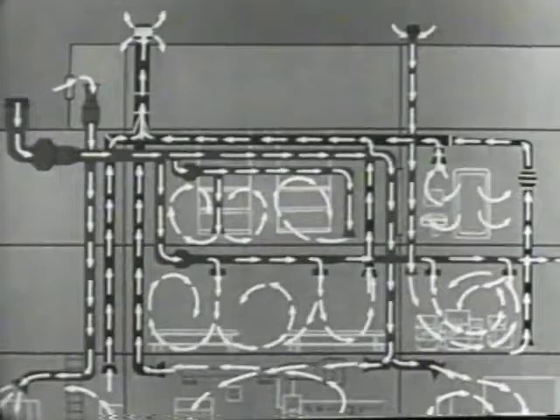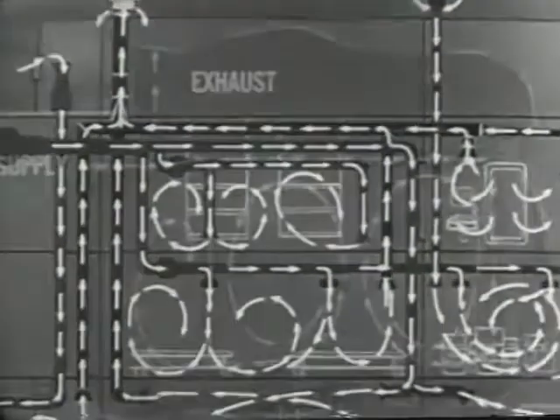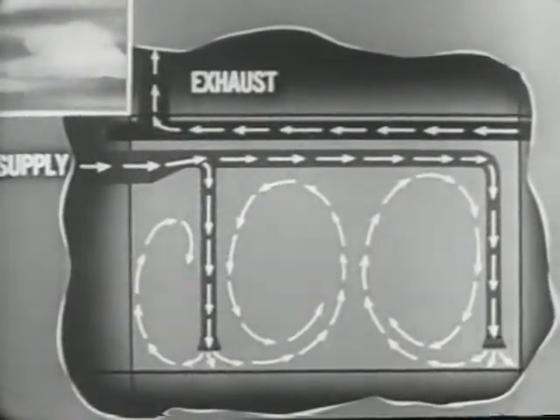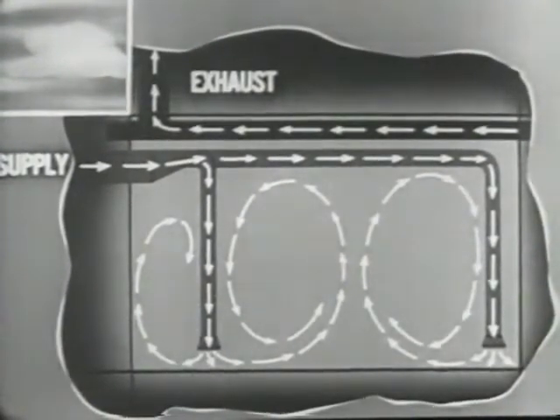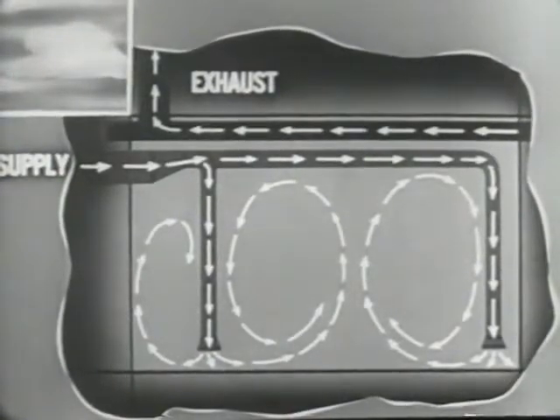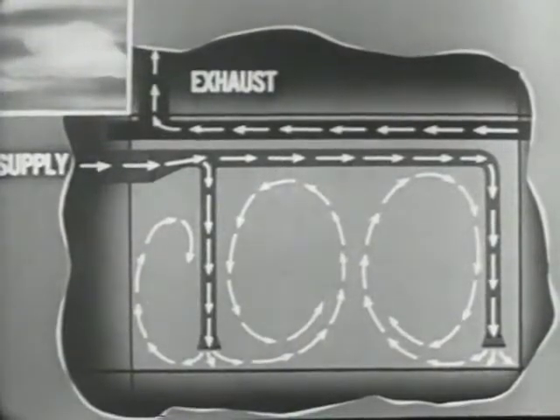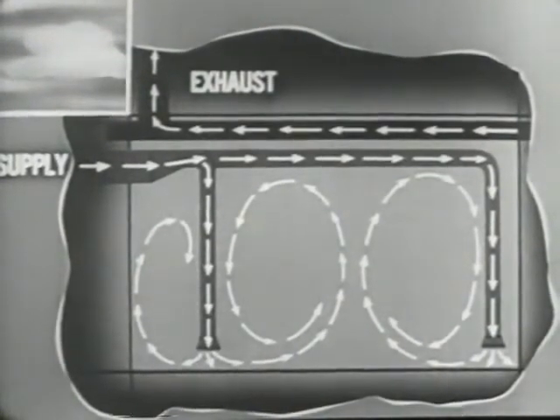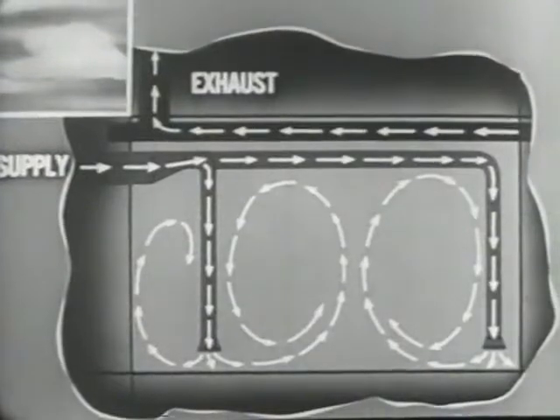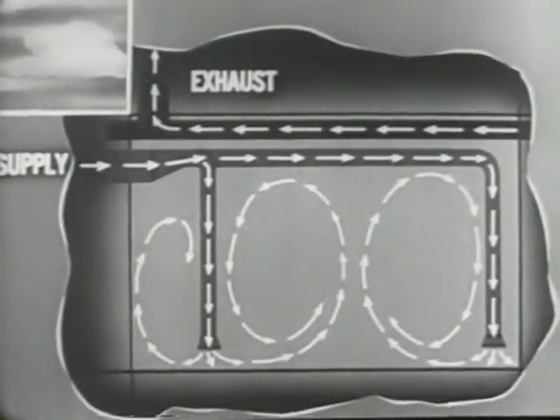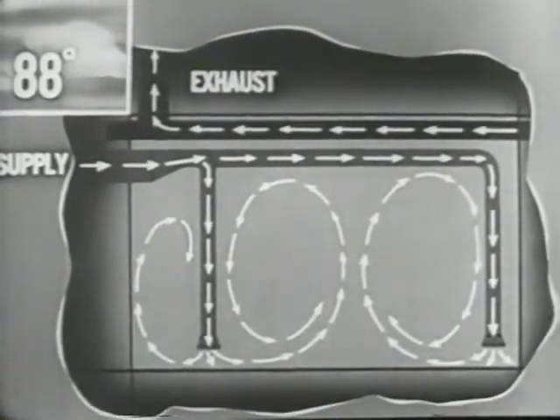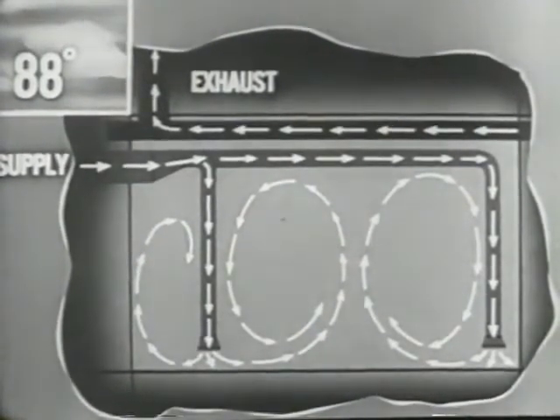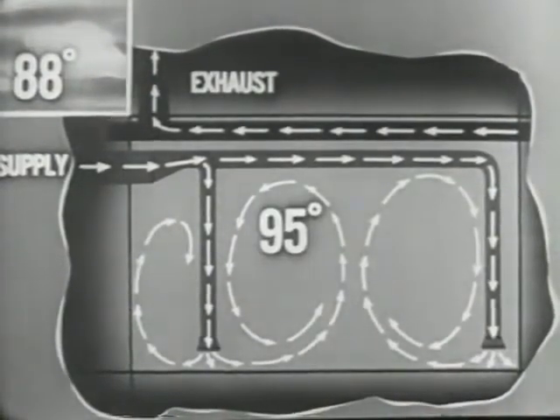Based on space usage, the temperature of ventilated spaces is determined by the amount and temperature of the air supplied. For example, the ventilation design for berthing spaces is based on air quantities to give an inside temperature in hot weather of 7 degrees above the outside temperature, the best that weight, space, and other technical considerations will permit. If the temperature of the outside air is 88 degrees, the temperature in the berthing spaces should be no more than 95 degrees.